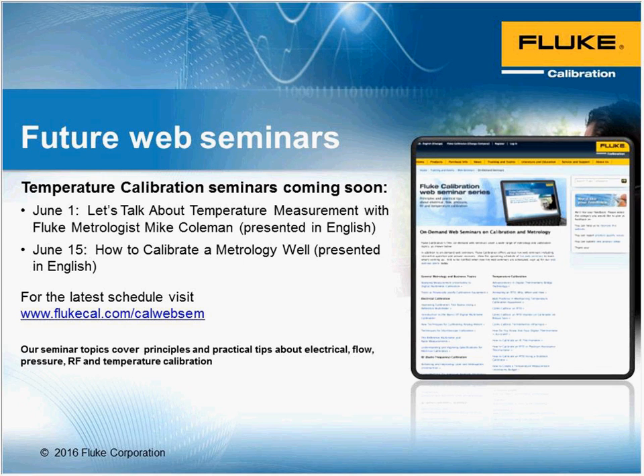The biggest thing that I've seen impact that is if you run a dry well to temperature, say you're running to 100 degrees, and now you take an ambient probe and place it in that. Basically, you've now added a cold mass to that unit. So it's going to take some time for that block to recover from the cold ambient temperature probe and then come back up to temp and stabilize. Again, most of the time it's fairly quick with a dry well.